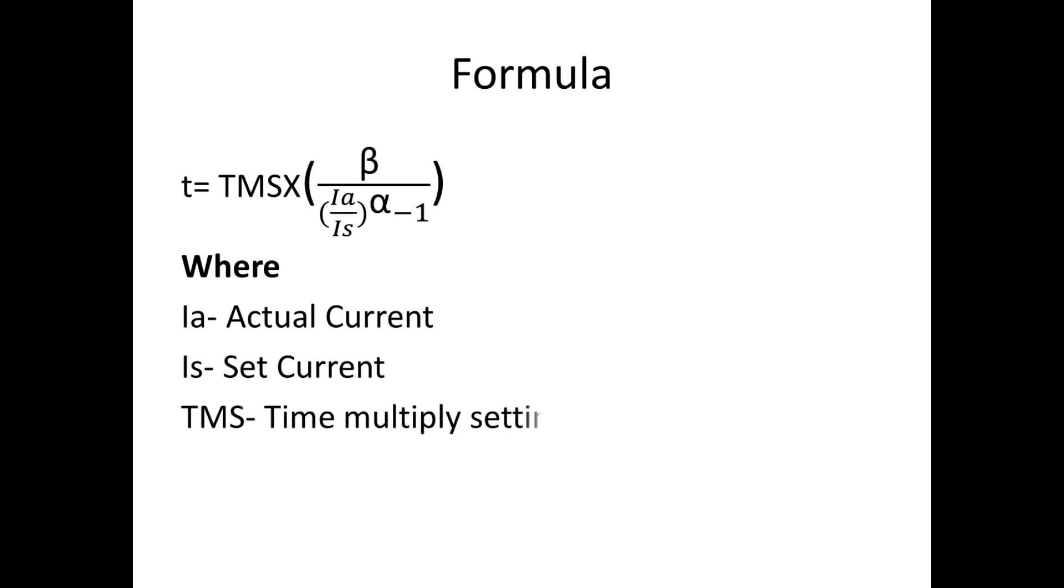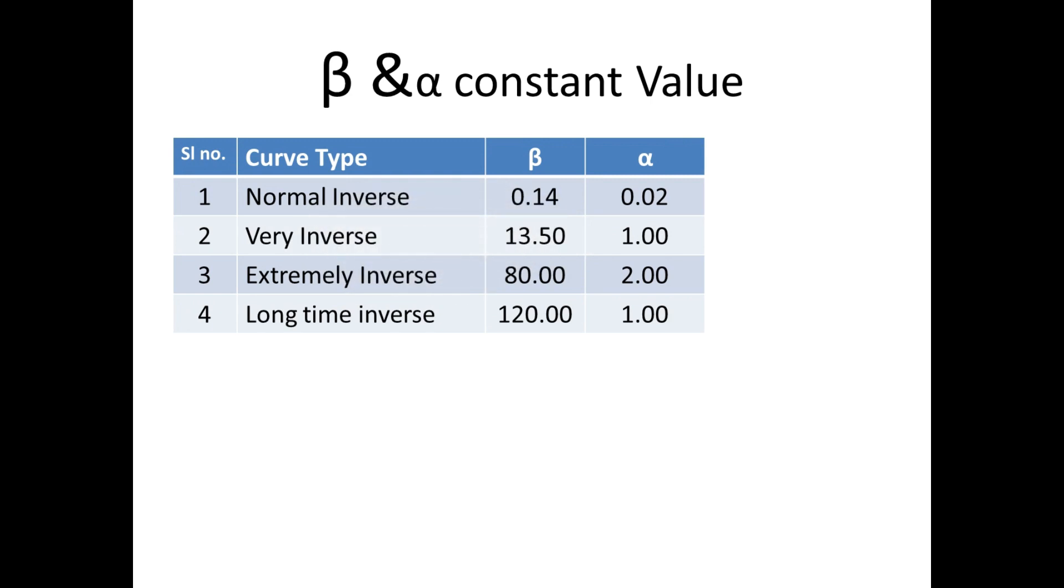Alpha and beta are constants which depend on curve type. These values are: for normal inverse beta is 0.14 and alpha is 0.02. For very inverse beta is 13.5 and alpha is 1. For extremely inverse beta is 80 and alpha is 2. For long time inverse beta is 120 and alpha is 1.